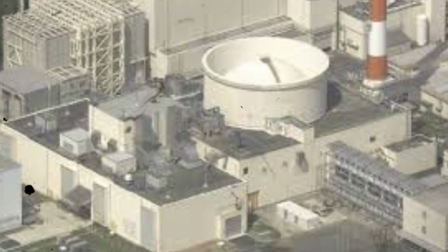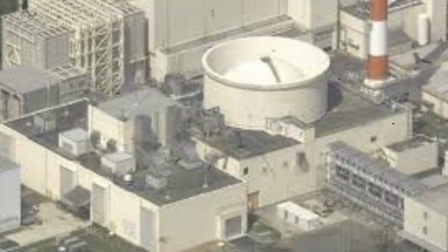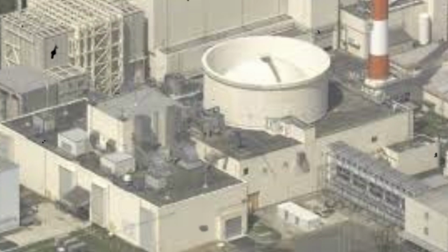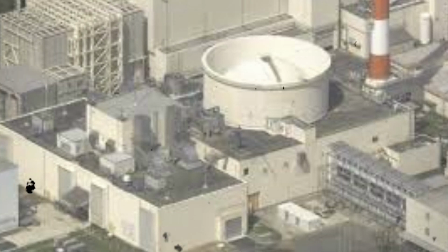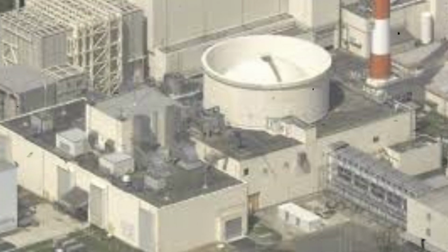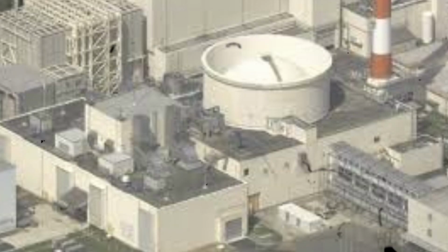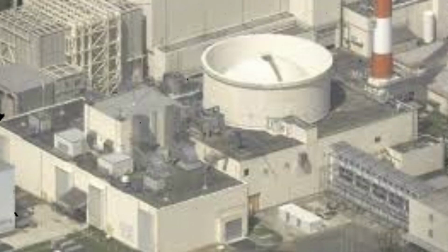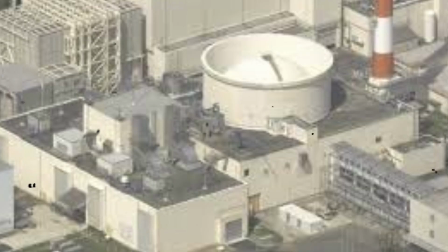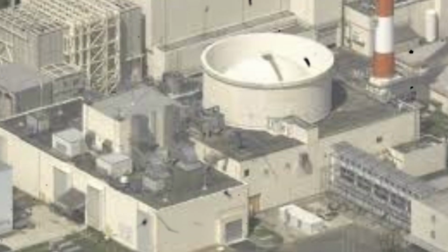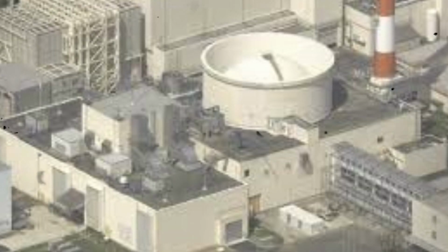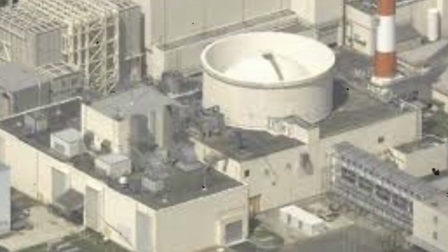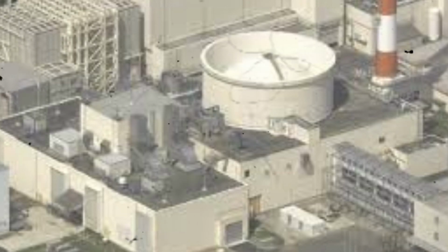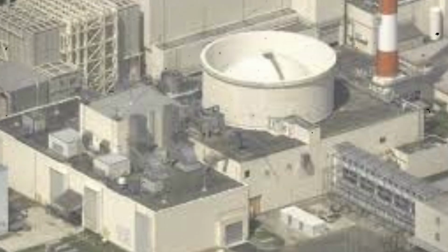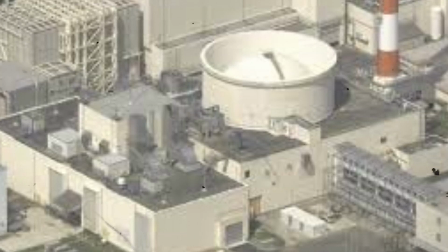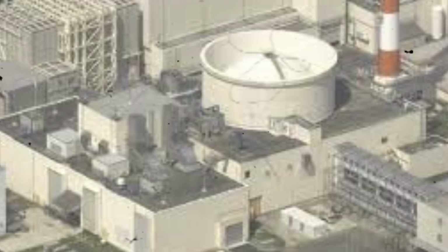Fatigue crack initiation occurred during an early period of 100% flow operation, when vortex shedding around the sharp taper geometry created oscillating stress concentrations at the root of the tapered section. The crack propagation proceeded gradually through subsequent operation at various power levels, with the crack front advancing through the well wall thickness at rates determined by the stress intensity and material properties under sodium environment conditions. The crack propagation process remained entirely invisible to plant instrumentation throughout its development.